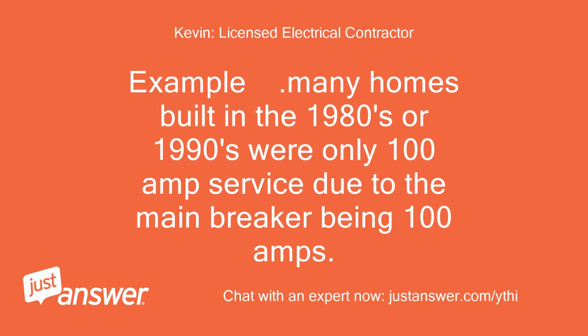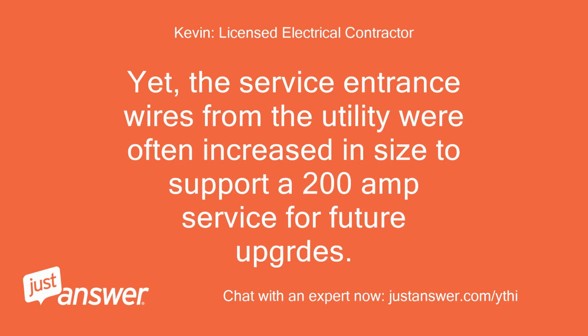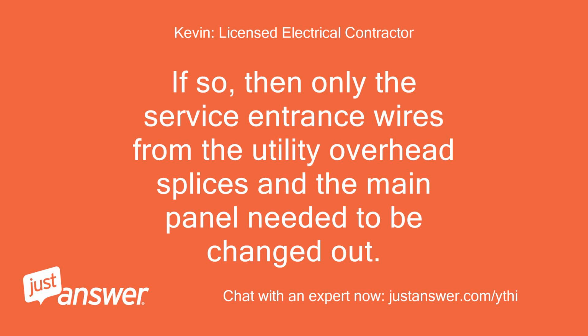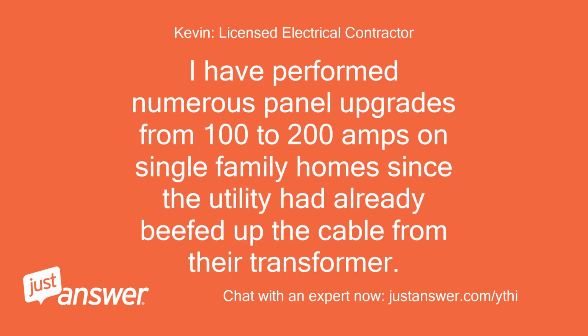Example. Many homes built in the 1980s or 1990s were only 100 amp service due to the main breaker being 100 amps. Yet, the service entrance wires from the utility were often increased in size to support a 200 amp service for future upgrades. If so, then only the service entrance wires from the utility overhead splices and the main panel needed to be changed out. I have performed numerous panel upgrades from 100 to 200 amps on single-family homes since the utility had already beefed up the cable from their transformer.